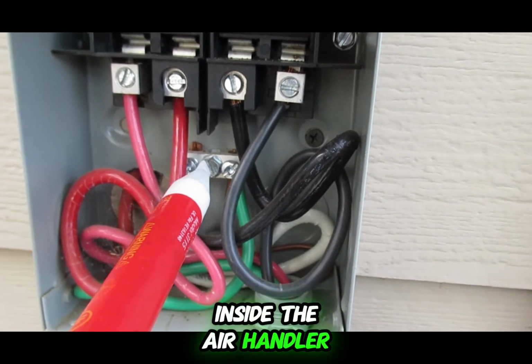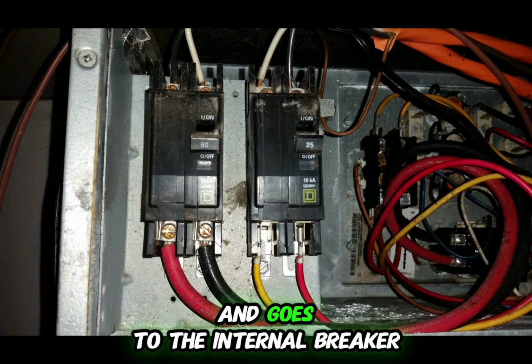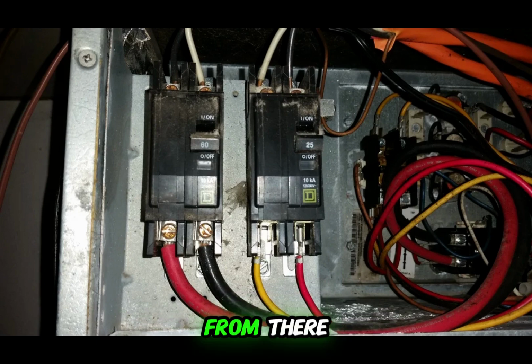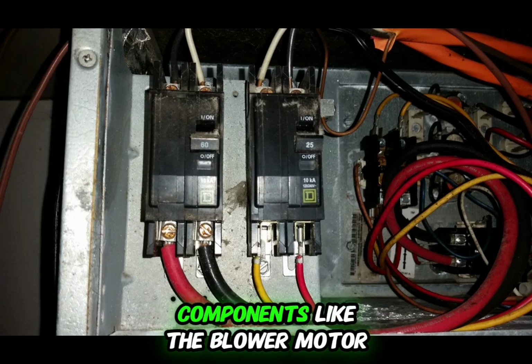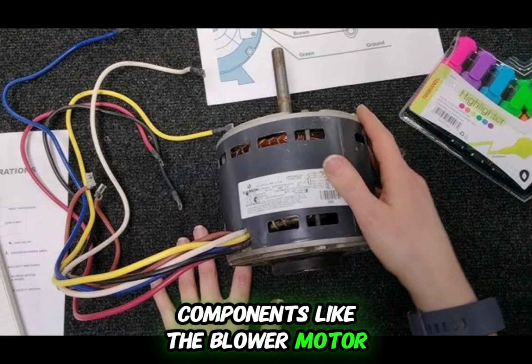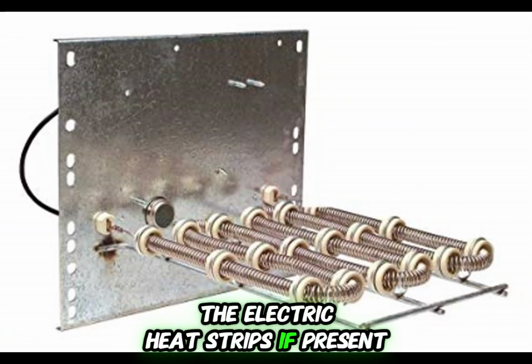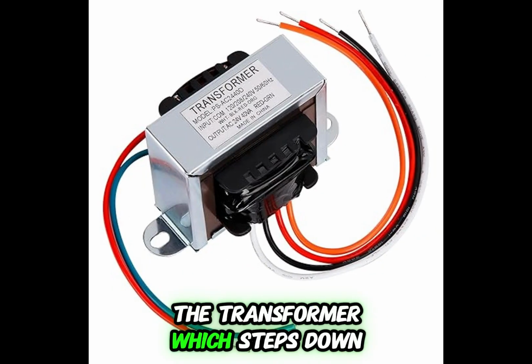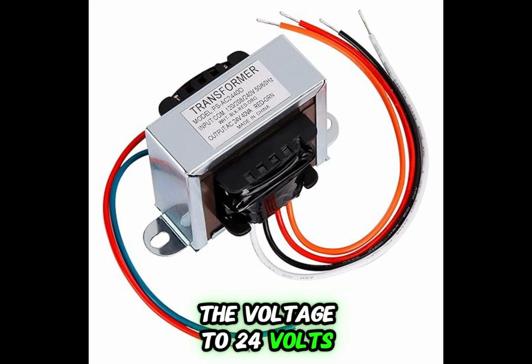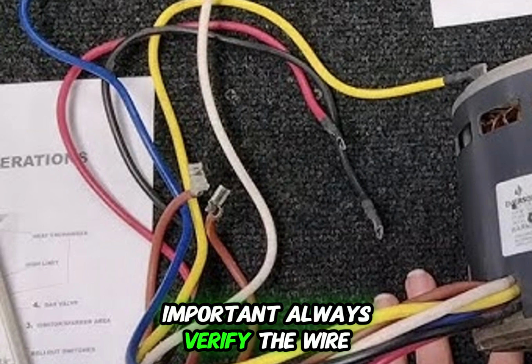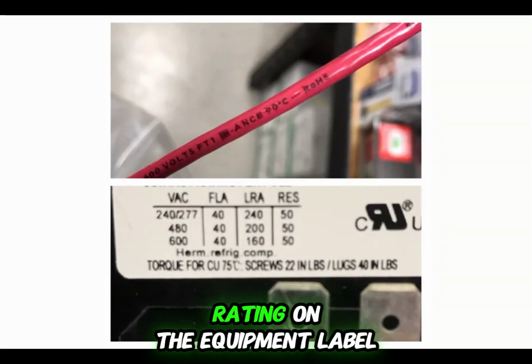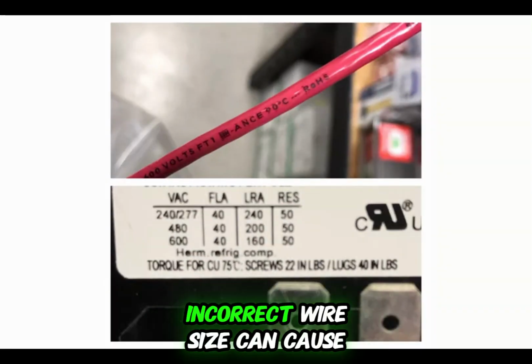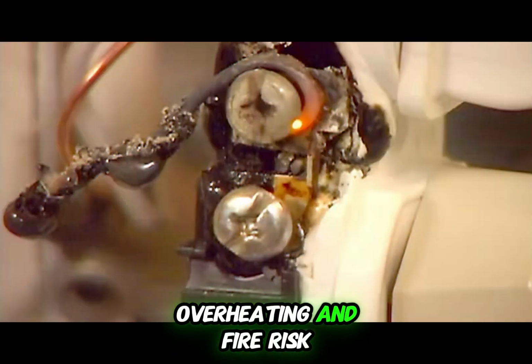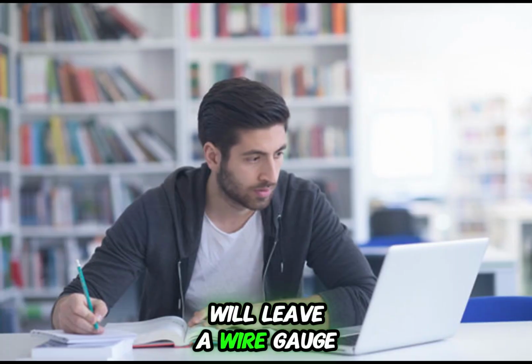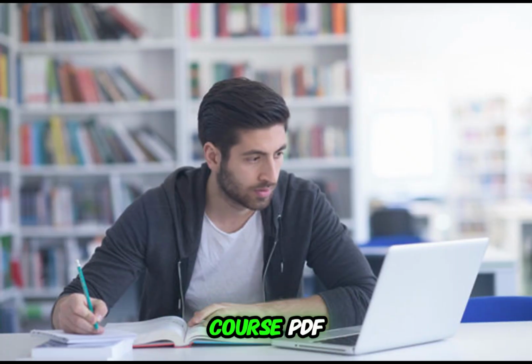Inside the air handler, power enters through the disconnect and goes to the internal breaker. From there, it connects to high-voltage components like the blower motor, the electric heat strips if present, and the transformer, which steps down the voltage to 24 volts. Important: always verify the wire thickness matches the amp rating on the equipment label. Incorrect wire size can cause overheating and fire risk. We'll leave a wire gauge and ampacity chart in the course PDF.